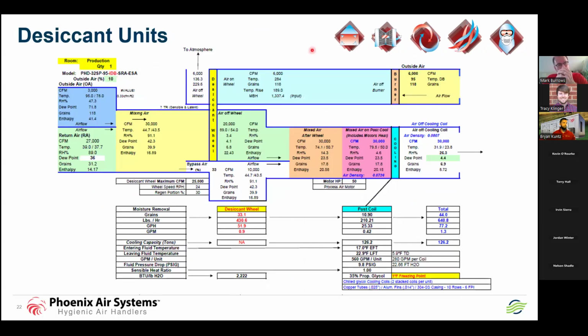If one says they want a desiccant, this is the sky's the limit on desiccants, right? How much moisture do you want to pull out? How many grains, and so on and so forth? How much air is going to bypass the wheel? This is quite the math equation, but again, the point is we can solve those problems as well. As far as solving the problem, I would like to suggest that not only do we offer the desiccant, can we do this with simple mechanical cooling and reheat coils? Can we achieve the same thing?